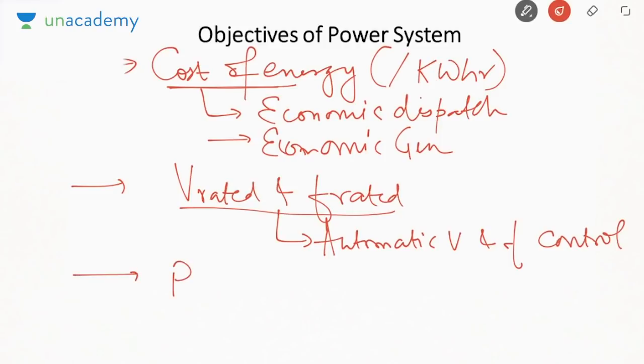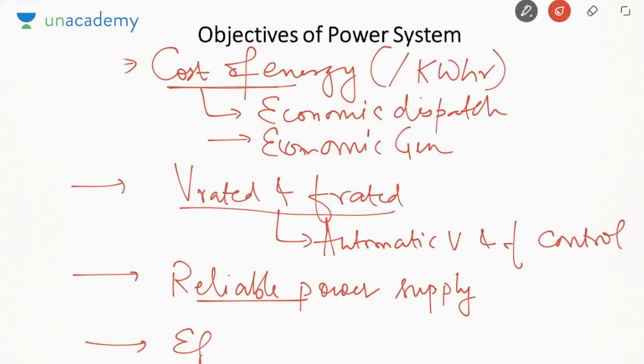Next is there should be reliable power supply. Okay, that means there must be lesser faults, or power supply must be continuous. Okay. So in this, generation and transmission are covered, that the power supply must be reliable. Okay. Next is effective protection. Why? So that my power system does not get damaged. If power system gets damaged, then what will happen? That equipment will become non-functional and there will be power shortage, or there will be power cut in certain areas. That is why protection must be good, so that no equipment or no apparatus gets damaged. Otherwise, there will be two effects.